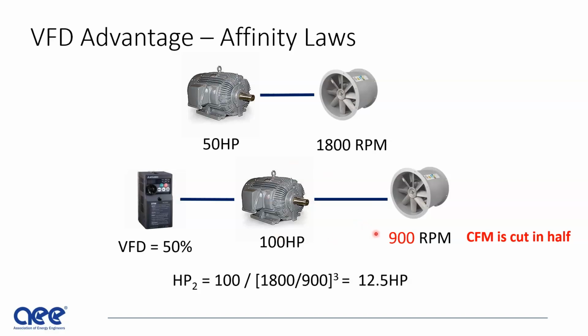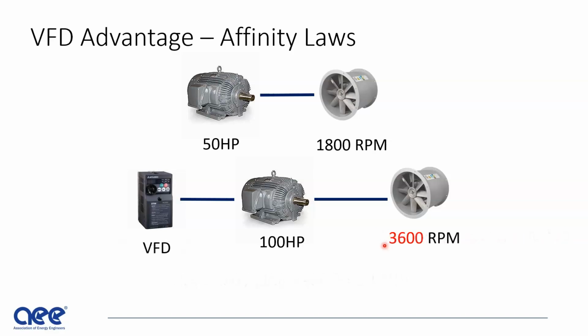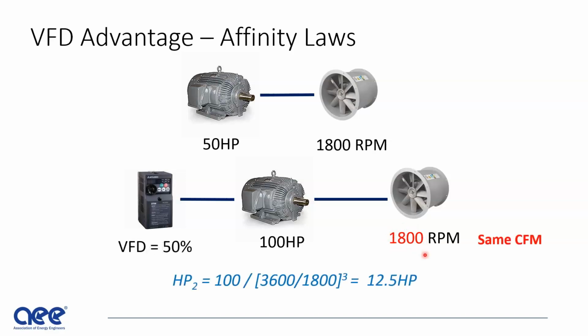So is there an arrangement where this could make sense from an efficiency standpoint? Well, what if we started with 3,600 RPM on the motor? Now, when we cut it to 50%, it's the same RPM as the original 50 horsepower motor. We're still at 12.5 horsepower resulting in the end, which is nice for the VFD. And we've now matched the load, so they're both 1,800 RPM delivering the same CFM. Of course, in this scenario, you say, well, gee, it really does make sense to buy a larger horsepower motor and use a VFD.